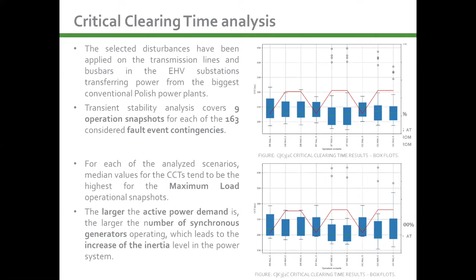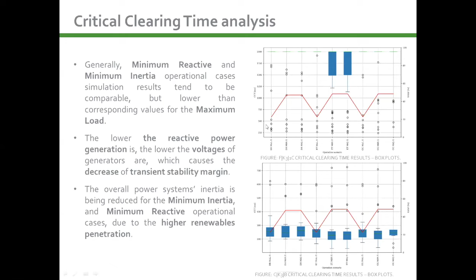Generally, for minimum reactive and minimum inertia operational conditions, simulation results tend to be comparable, but lower than corresponding values for the maximum load. The lower the reactive power generation is, the lower the voltages of generators are, which causes a decrease of transient stability margin for those generators. The overall power system's inertia is being reduced for the minimum inertia and minimum reactive operational cases due to higher renewables penetration. So there's an indirect correlation between those measures.